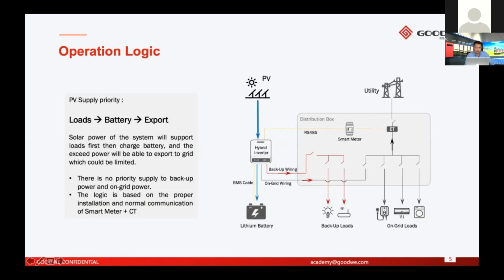So what's the priority? The priority is they will support loads first, and then if there is enough power, they will charge the battery. Then the excess power will be exported to the grid. Of course, for hybrid systems, you can choose to allow the system to export to the grid or not. This is called the zero export function. This is what Lucas told you guys.